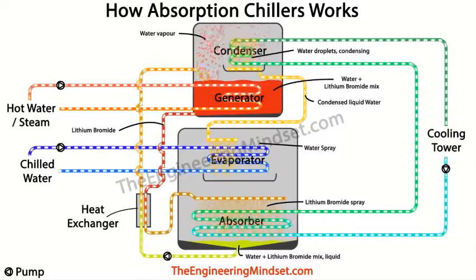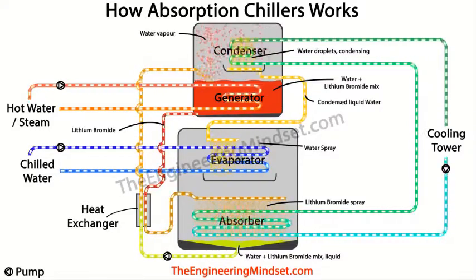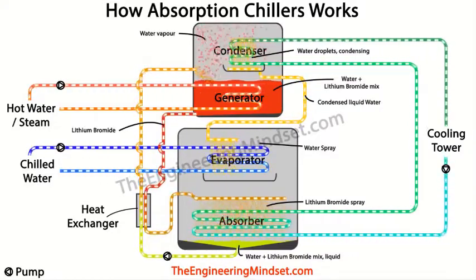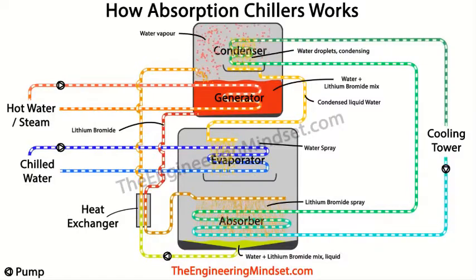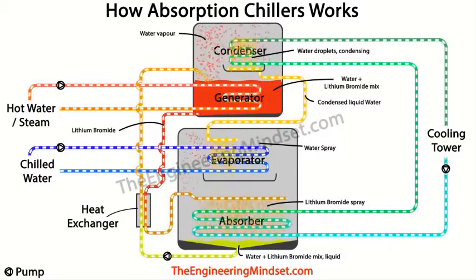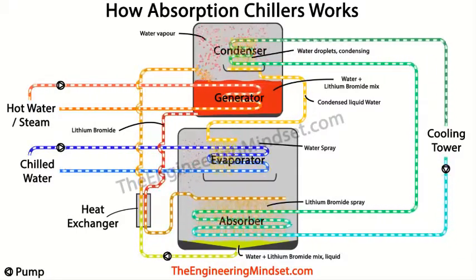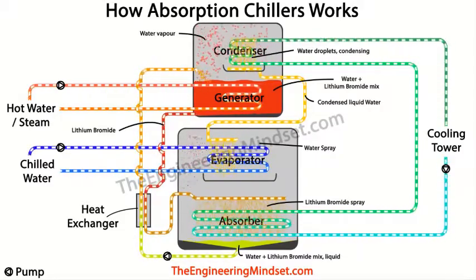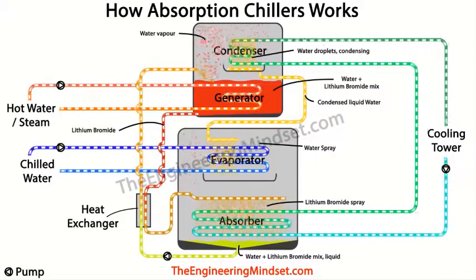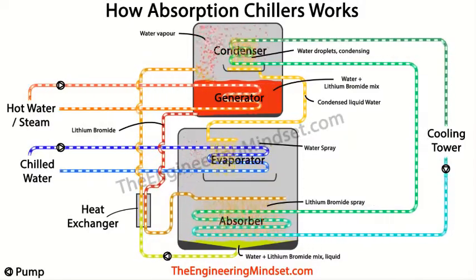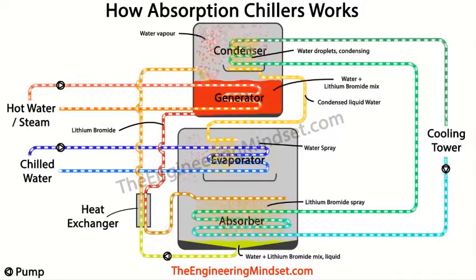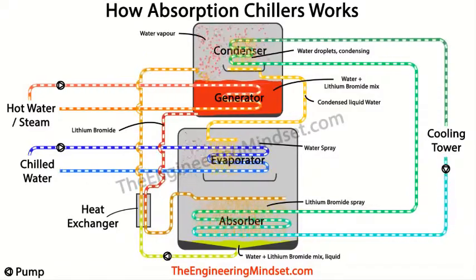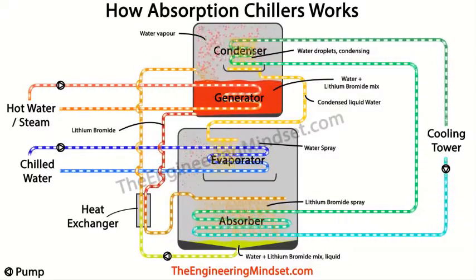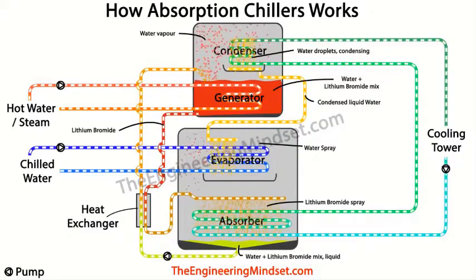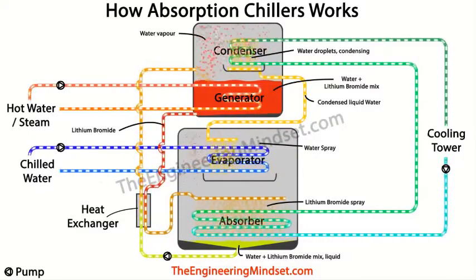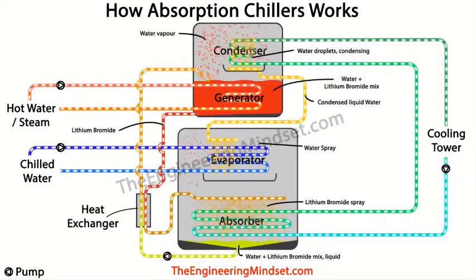So this cold condensed water will spray over the chilled water tubes and cover the surface of the tube with a thin film of cold water. The chilled water will enter at around 12 degrees Celsius, 54 degrees Fahrenheit, and this will transfer its thermal energy, its heat, all the unwanted heat from the building. It will transfer that through the tube wall and into the low temperature water film, which was sprayed across the outside of the chilled water tubes. Remember, the two waters never mix, they're always kept separate, and they are separated by the pipe wall.